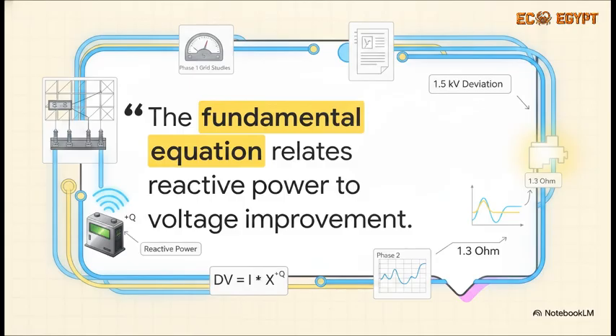I want to focus on Profile 2 for a second because honestly, this is where a lot of junior designs just fail. Grid reactance is mathematically vital here. The training specifies that the 1.5 kilovolt voltage deviation and the 1.3 ohm grid reactance, which you find during Phase 1 grid studies, those directly feed our reactive power calculations in Phase 2. The BESS isn't just mindlessly dumping raw energy. It is precisely injecting reactive power to push the local voltage back into compliance right through that 1.3 ohm impedance.